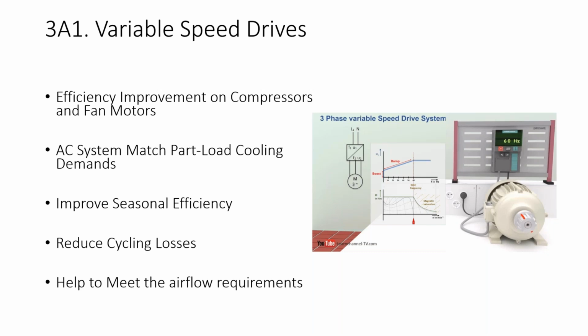It also matches part load cooling demands. It improves seasonal efficiency, and it also reduces cycling losses. So just in case we don't have a variable speed drive, and you're going with a one-speed compressor or fan, what's going to happen is that whatever the load is, the fan will go full blast and supply the air and the cooling. And when it isn't required, the fan will shut down. It's cycling between on and off, which creates a lot of losses in terms of electricity. And to avoid those losses, we use variable speed drives, which reduce the cycling losses.